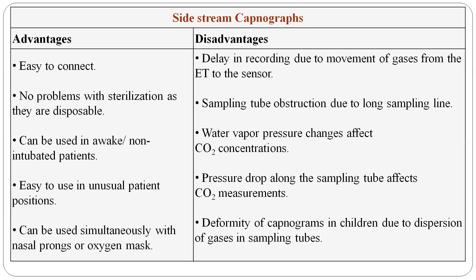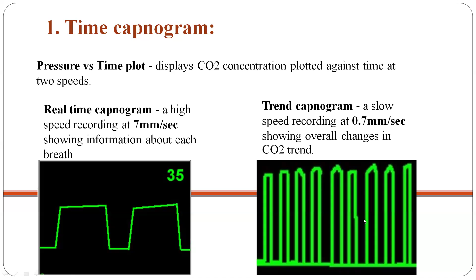Coming to components, there are two components, time and volume component. In time component, pressure is plotted against time, and it displays carbon dioxide concentration against time at two different speeds. One is the real-time capnogram and the other one is the trend capnogram. In real-time capnogram, a high-speed recording at 7 millimeters per second is taken. It shows information about each breath. And trend capnogram is a slow speed recording at 0.7 millimeters per second, and it shows overall changes in the carbon dioxide trend.